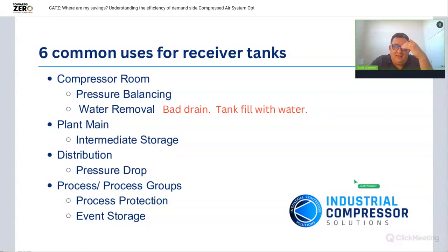I would assume that every single person in this group right now has been in a situation where they're standing in front of a receiver tank, but the system does not look like there's a receiver tank. And that's because it's full of water. There is no storage.